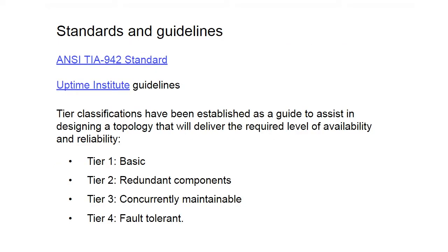Now there's two standards that are basically used for standby systems for mission critical, private: that's the ANSI TIA 942 standard and then the Uptime Institute guidelines. Both of these have tiers or levels or classifications which have been established. They're basically to be used as a guide to assist you in designing the topology and the system that will deliver the level of required redundancy and reliability that you want. And they're basically broken up into, like I said, tier classifications.